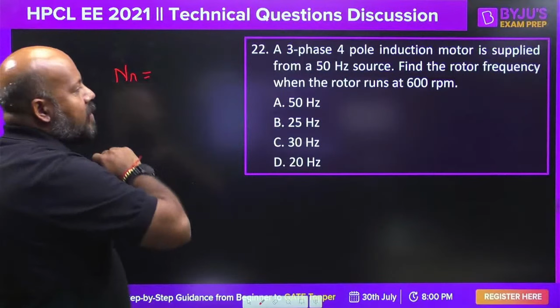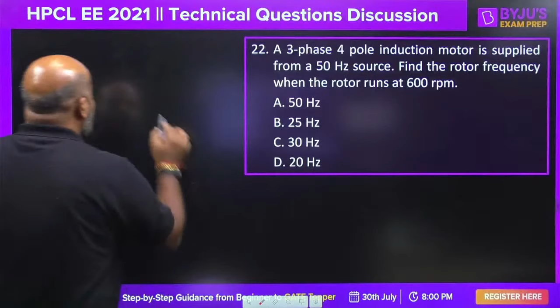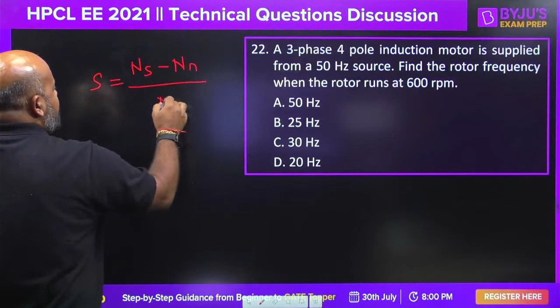He is asking the rotor frequency, so first find the slip. Slip equals synchronous speed minus rotor speed, divided by synchronous speed. Synchronous speed is 120 times frequency divided by poles. Operating frequency is 50 Hz, number of poles is 4, so synchronous speed is 1500 RPM. So slip equals 1500 minus 600 (rotor speed), divided by 1500, which is 900 upon 1500.